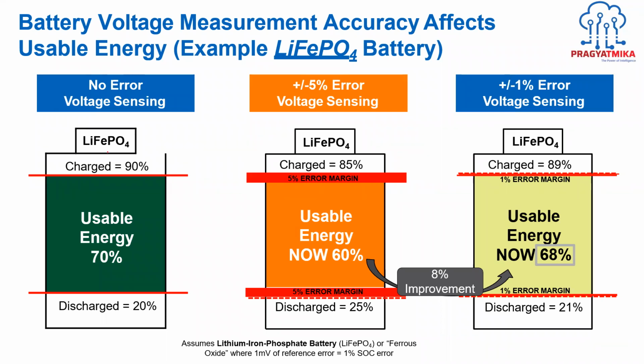So here I've taken an LFP battery pack, LiFePO4. The discharging is minimum up to 20%, and maximum we are charging up to 90%. That's the usable energy, that's 70%. As you know, for lithium-ion battery packs, we don't charge up to 100% to make the life of the battery pack longer. So 20 to 90 is the standard we are keeping. Generally we keep it up to 80% only, but here in this example, 20 to 90, I'm keeping it for reference purposes. So if there is no error in voltage sensing, that's the ideal condition.